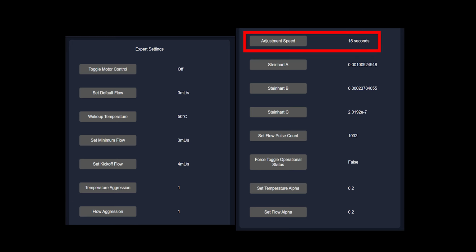Adjustment speed represents how much time needs to pass before ATACC will check the target and actual temperatures and see if a correction needs to be made. The smaller you make this number, the more responsive ATACC gets, but it also gets less stable and prone to overcorrections. The larger you make the number, the more stable it will be, but slower to react to changes. If ATACC is overcorrecting itself and it's resulting in the temperature constantly overshooting and then undershooting, you should increase this number. Keep in mind this number only affects the temperature corrections. Flow corrections currently happen at a fixed rate of once every second.